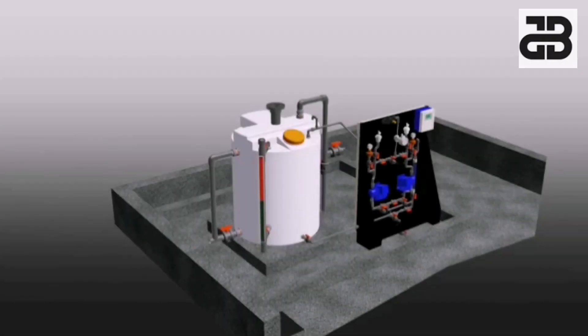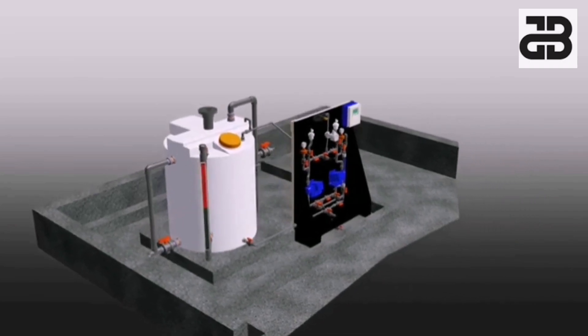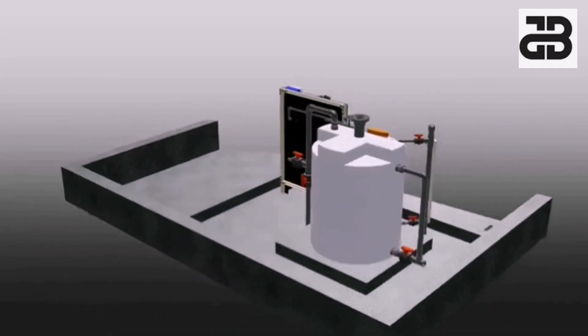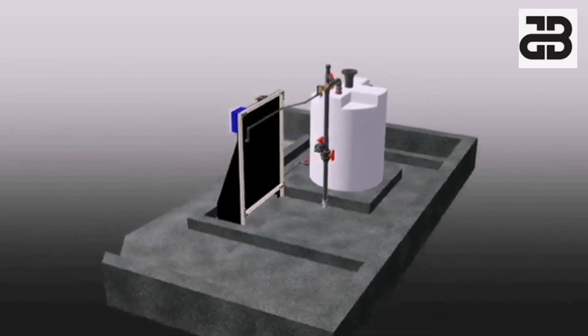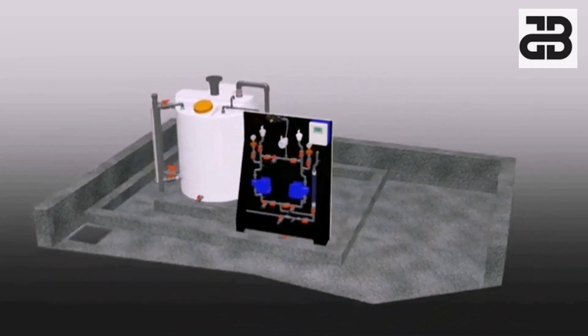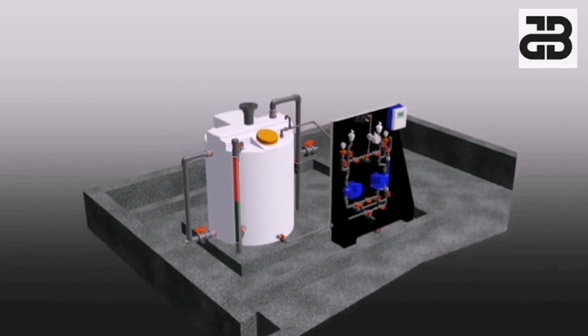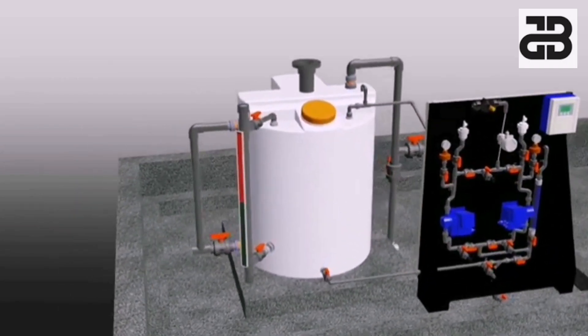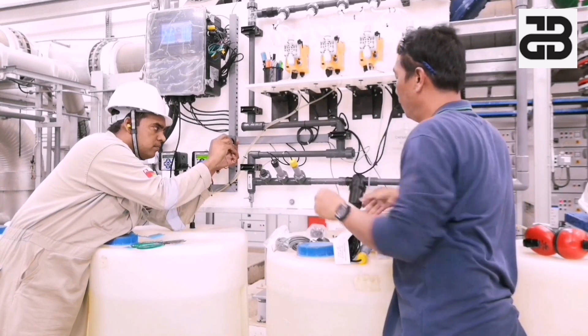Parts of a chemical dosing system include: a chemical container or tank that holds the product to be dosed; a pump that varies in materials and size; an inlet suction line; a dosing line injector; and a one-way valve where the chemical is injected, allowing chemical into the liquid flow even as it overcomes pressure in the pipe.